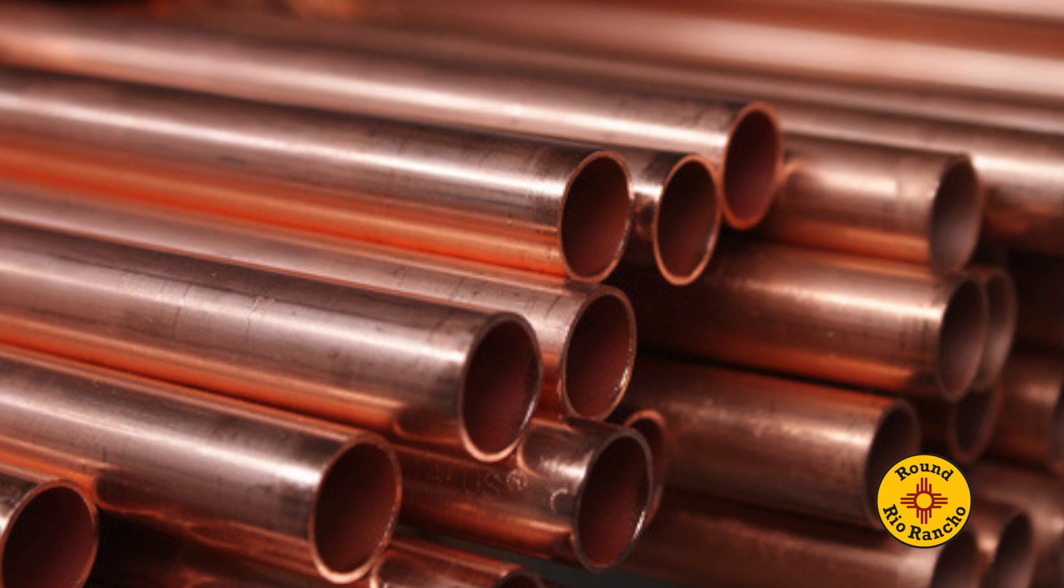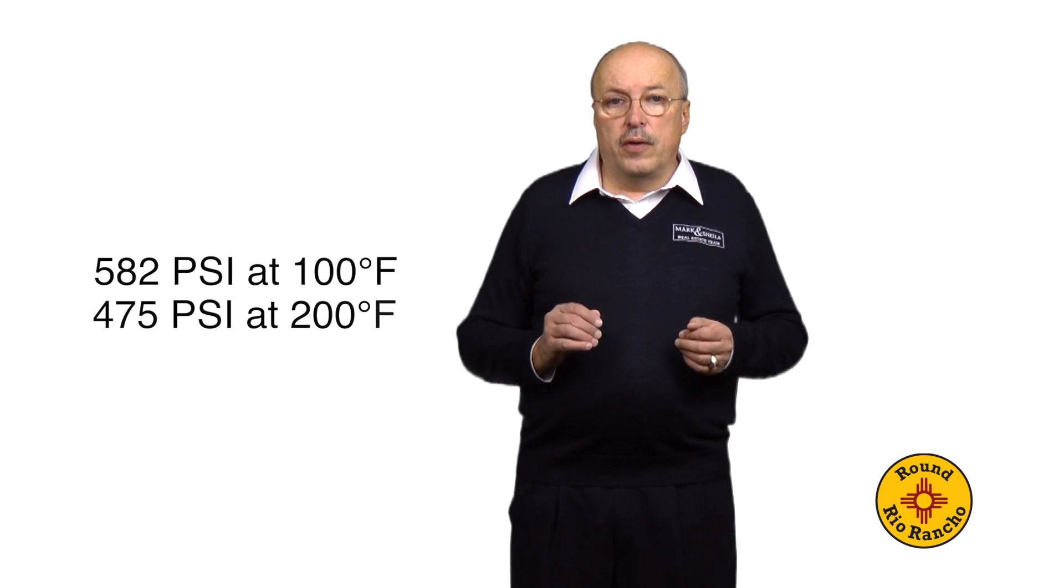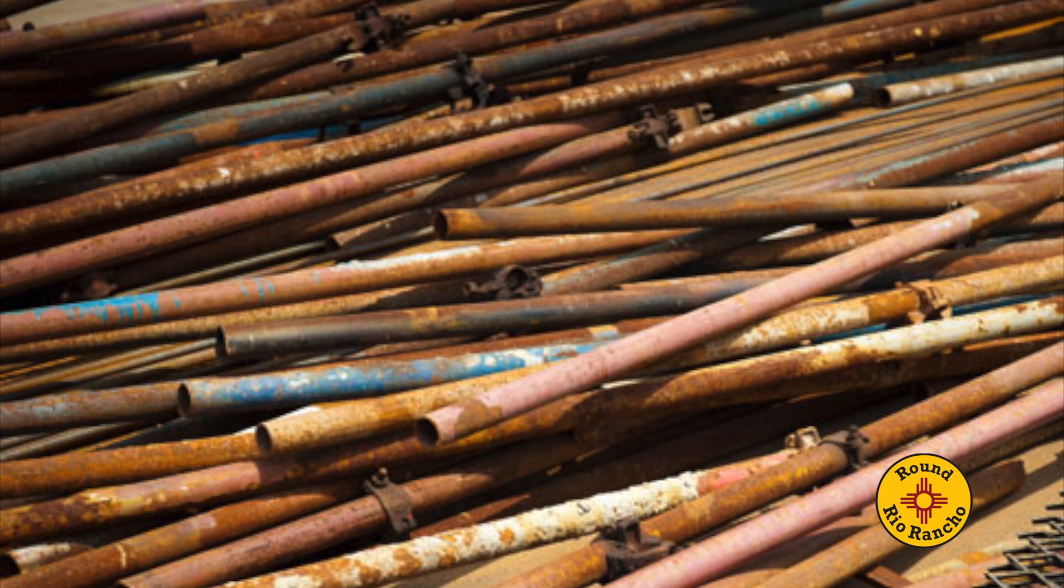The gold standard was and still is type L copper pipe. This is slightly thicker than type M and will probably last longer. The cost of copper has shot up in recent years and proper installation requires some skill and experience as joints need to be made using solder and a torch. It's pressure rated at 582 psi at 100 degrees Fahrenheit and 475 psi at 200 degrees. If the home is on a raised foundation and the plumbing is in a crawl space below, be sure to secure the access as thieves have been known to tear out copper plumbing for the scrap value if they can get to it. Copper pipe is very thermally conductive and is subject to damage from freezing.